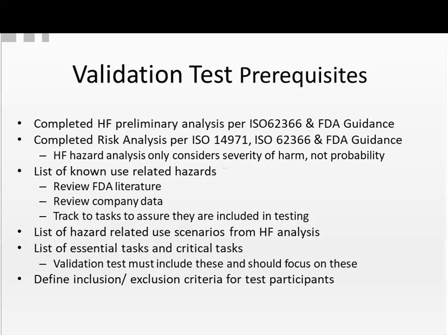The prerequisites for actually conducting the validation test. You should have completed human factors preliminary analyses following the ISO and the FDA guidances. You should have a completed risk analysis following ISO 14971, keeping in mind that the human factors hazard analysis considers only severity of harm, not probability.